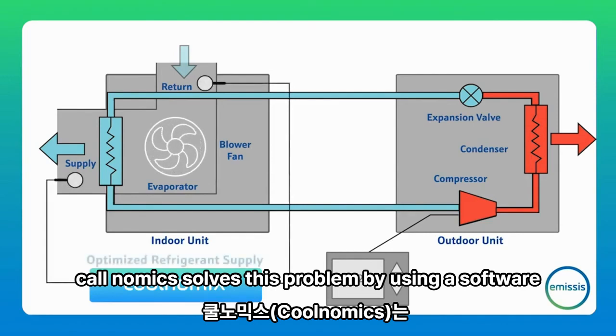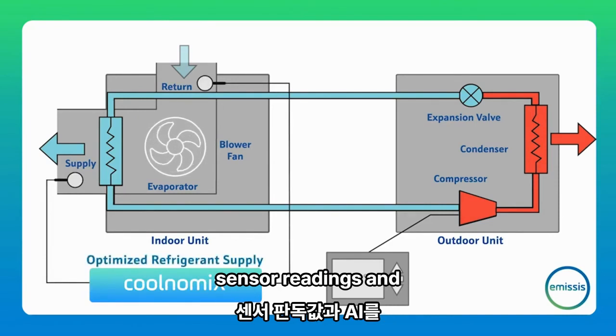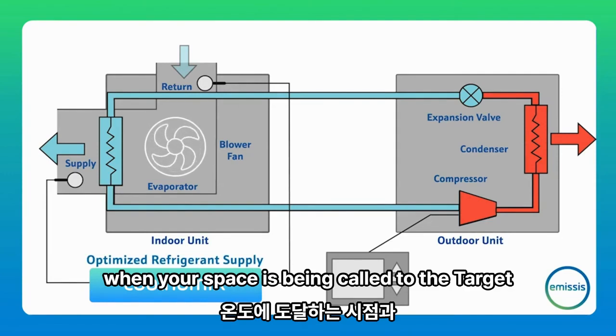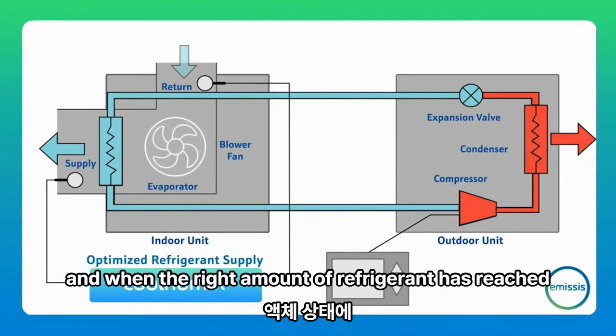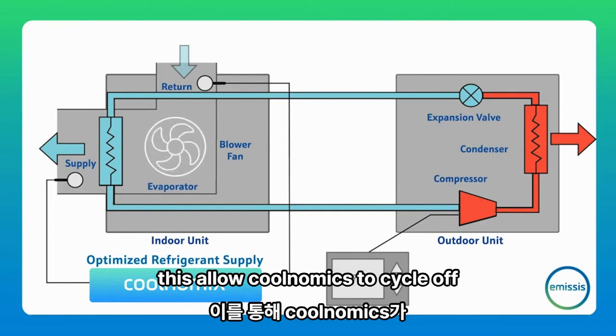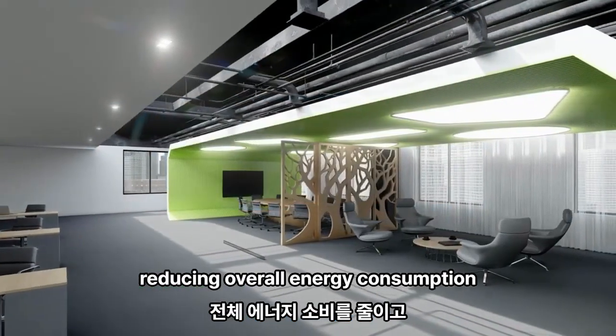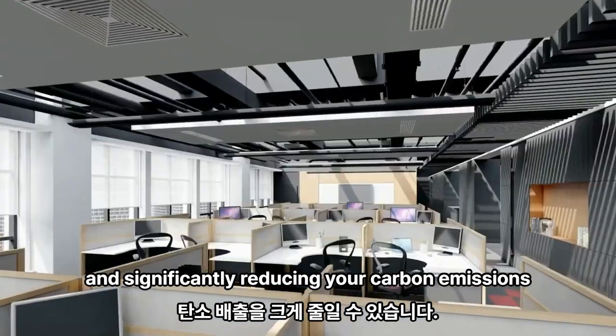Coolnomix solves this problem by using a software algorithm called Optimised Refrigerant Supply. It uses sensor readings and AI-based predictive analysis to determine when your space has been cooled to the target temperature, and when the right amount of refrigerant has reached a high pressure liquid state. This allows Coolnomix to cycle off the compressor at the optimal time, reducing overall energy consumption and significantly reducing your carbon emissions.